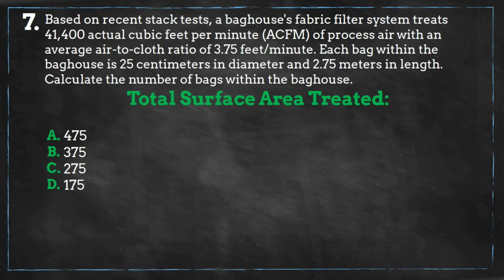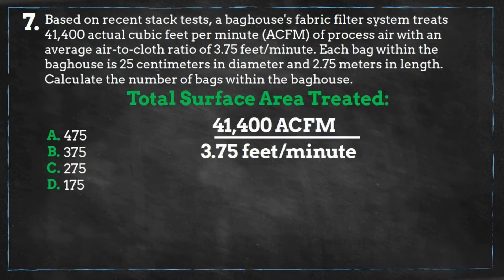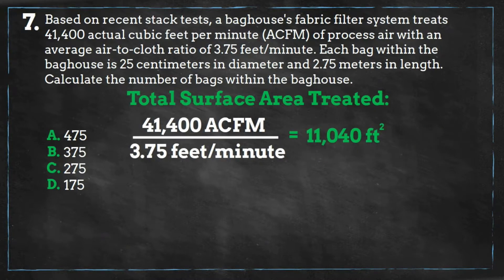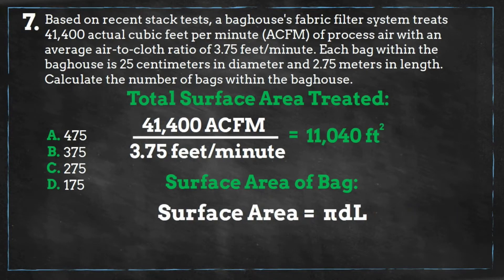The first thing you should do is find the total surface area treated. Take your flow rate and divide it by your velocity, and you'll get a surface area treated of 11,040 square feet.